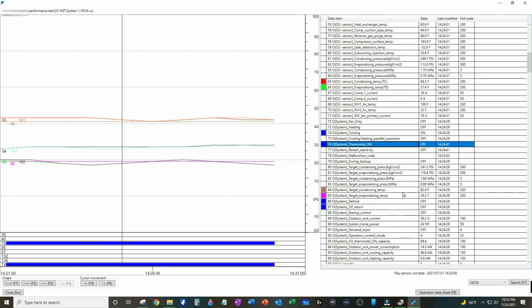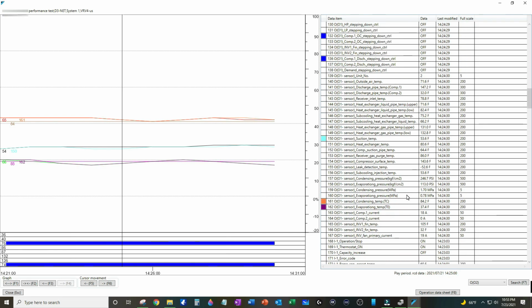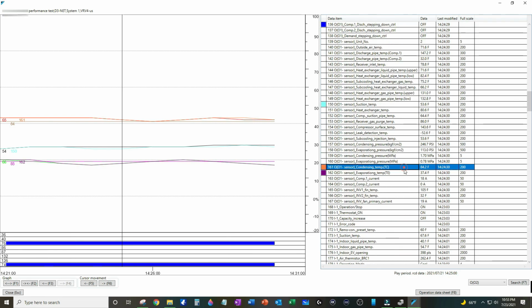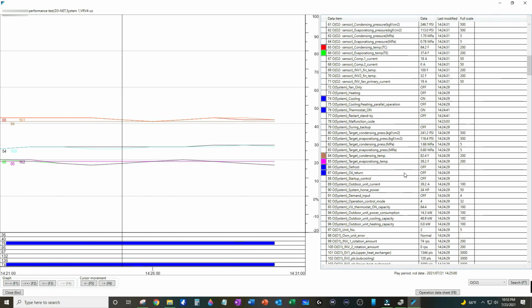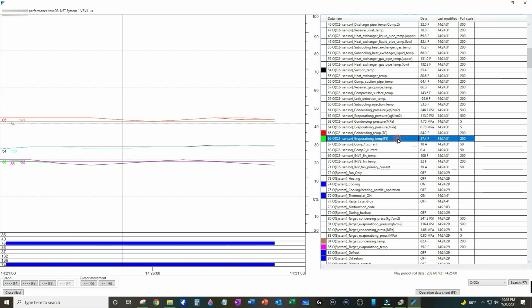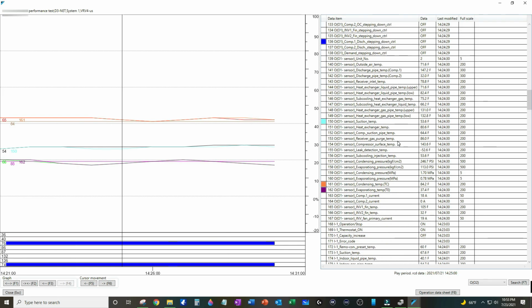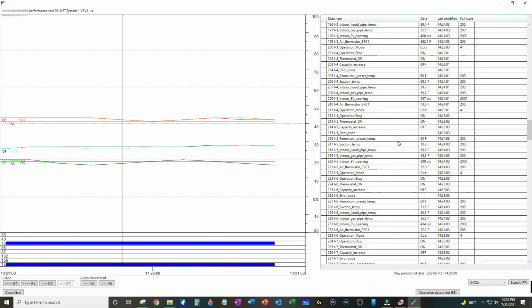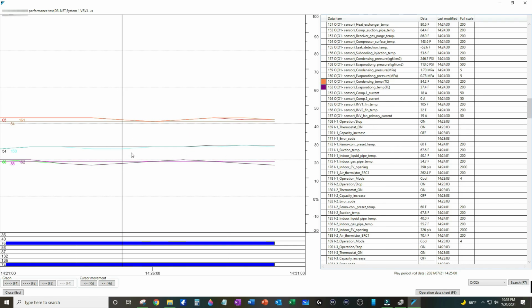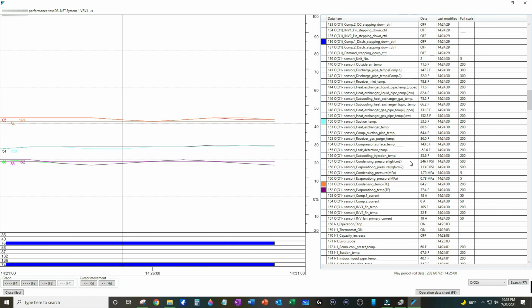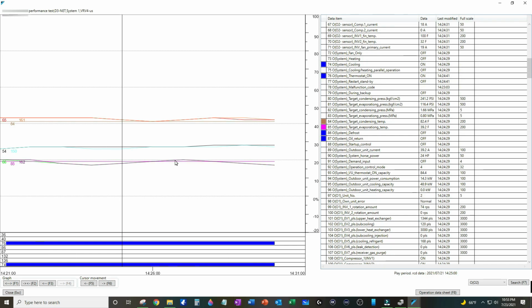I also like to plot the target condensing and evaporating temperatures and the actual condensing and evaporating temperatures of each outdoor module as well, so I can see how close to targets the system is maintaining. This also helps a ton while scrolling through all the data points, because if the system shuts off or changes modes suddenly or goes into oil return or defrost, I can immediately see the change on the graph, which flags my attention. That way, I'm not misanalyzing the data points that I'm scrolling around looking at.